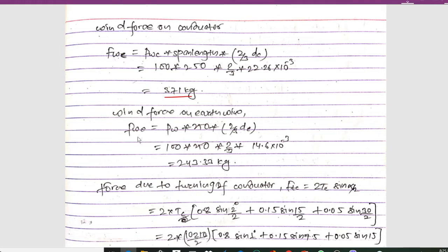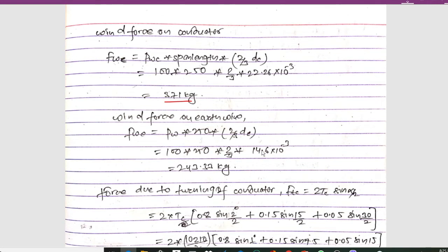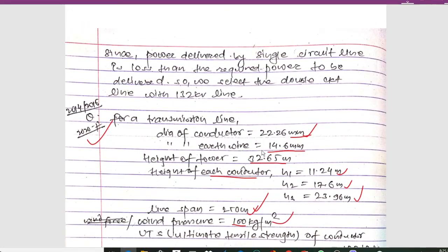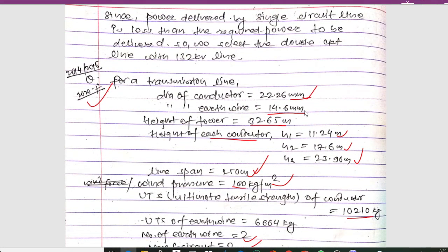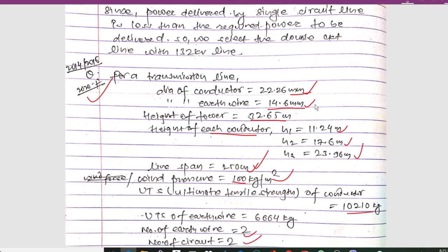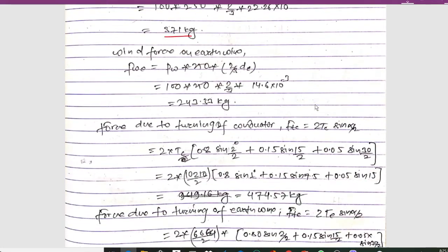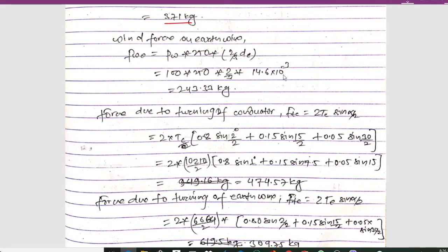Similarly, wind force on earth wire (FWE) is calculated as: FWE = Pw × span length × (2/3) × D. Using Pw = 100, span = 250 m, and earth wire diameter D = 14.6 mm, we get FWE = 243.33 kg.